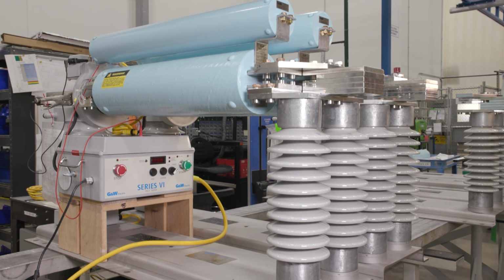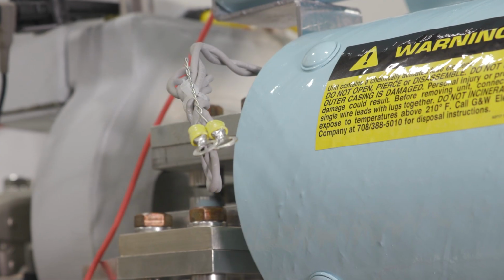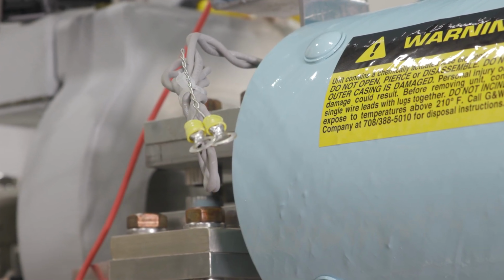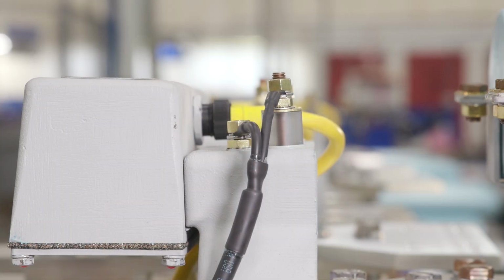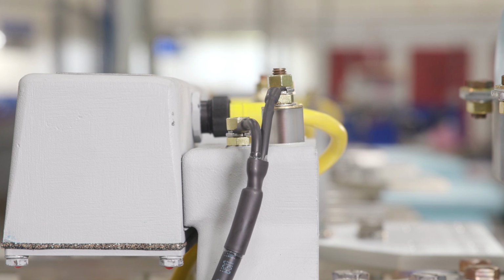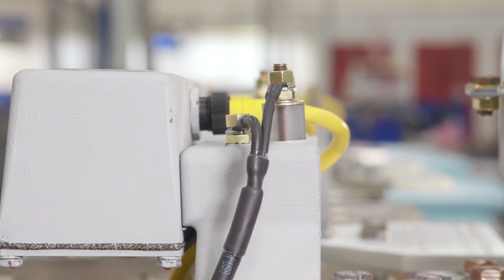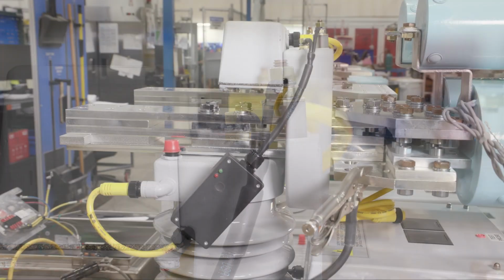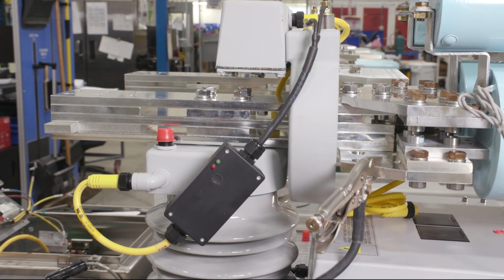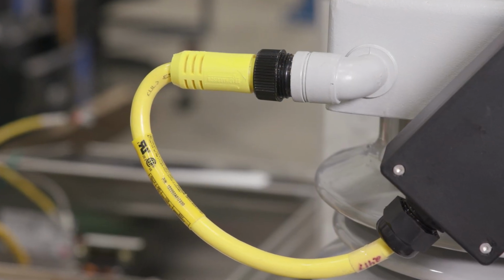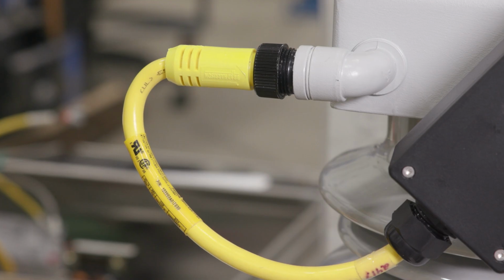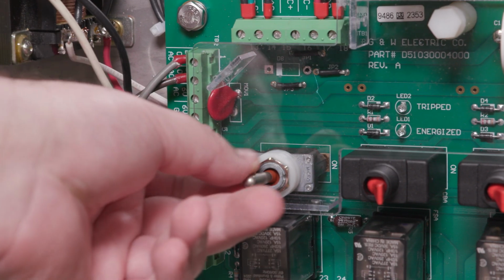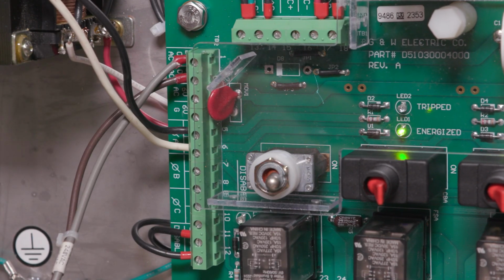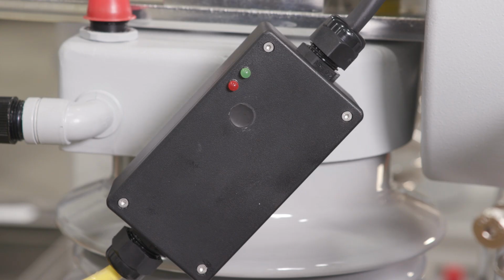Next, keep the system de-energized and the interrupter leads shorted and isolated from the SFL. Connect the cable of the simulator firing leads with the ring terminal to the SFL triggering terminal. Then connect the yellow simulator cable to the remote indication terminal of the CLiP current limiting protector isolation transformer. Now enable the power to the CLiP current limiting protector control box. A green light in the simulator indicates that it's powered up.